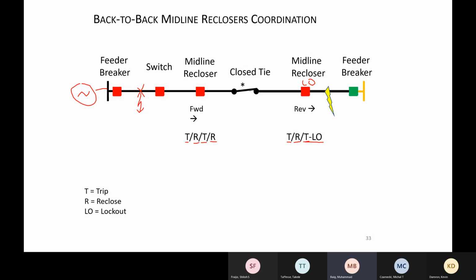Okay, now I understand. So we have a source only on this end, and we don't have a source on the other end? Well, you do. Okay, but in this application, we're open right here, right? Yes. That's what the green is, open. Okay, so if everything is closed and the fault is on the left side that you have already shown with your markup, if the fault is there. The only time we have this closed, fed from both ends, is during switching.